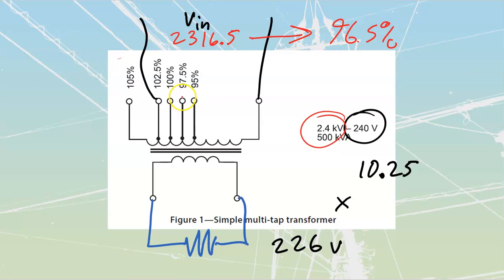If I go to a slight bit higher, 97.5%, I'm still going to come in a little bit low. If I go to a little bit lower, then I'm going to come in a little bit high on this side. Generally speaking, it is better to be a slight bit low than it is to be a slight bit high. So I'm going to take my tap and move it over to the 97.5%. And at that point, I would once again recalculate to figure out what I'm going to change this to.